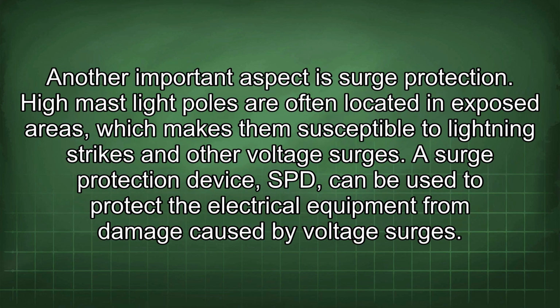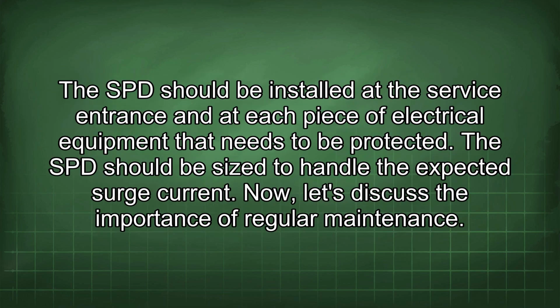Another important aspect is surge protection. High mast light poles are often located in exposed areas, which makes them susceptible to lightning strikes and other voltage surges. A surge protection device, SPD, can be used to protect the electrical equipment from damage caused by voltage surges. The SPD should be installed at the service entrance and at each piece of electrical equipment that needs to be protected. The SPD should be sized to handle the expected surge current.